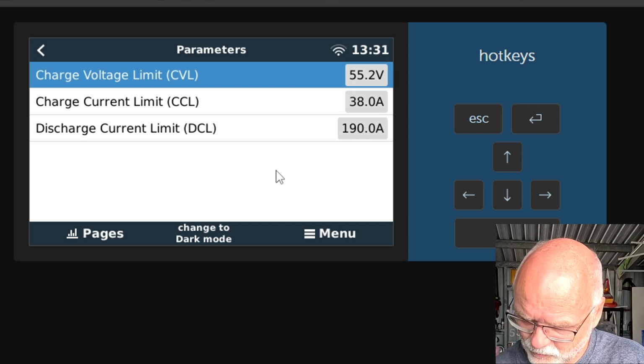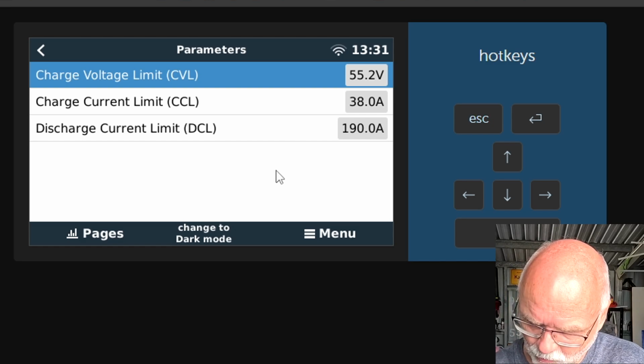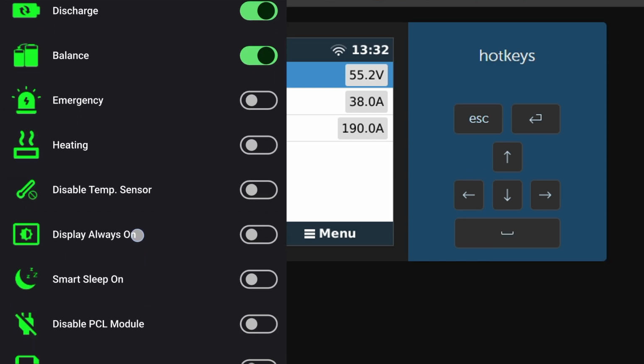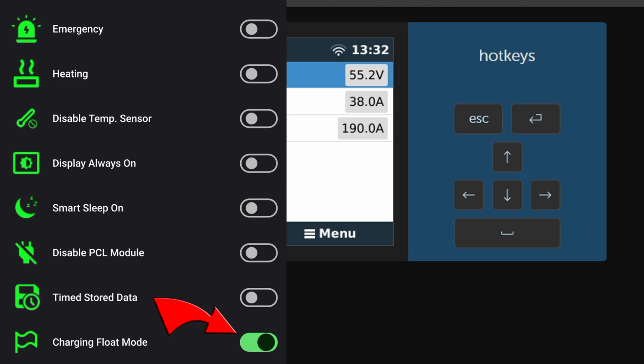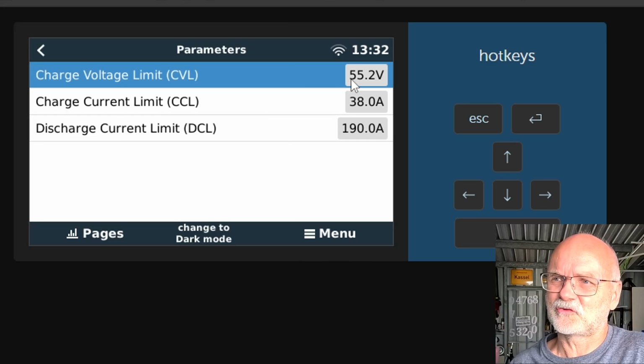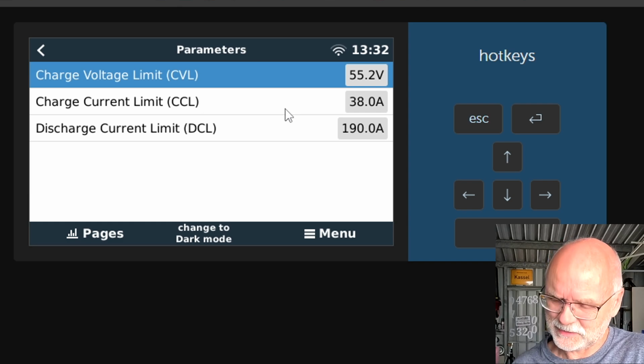One thing I need to check, of course, is do we have float mode actually enabled? Yes, we have — go into controls and check if charging float mode is enabled. Yes, it is turned on, but it does not seem to request a float charge anymore. So these nice people are right, we have another bug in the JK Inverter BMS. Wow, float mode is not working anymore, it's not triggering anymore. We are staying in bulk regardless of whether float mode is turned on or not.